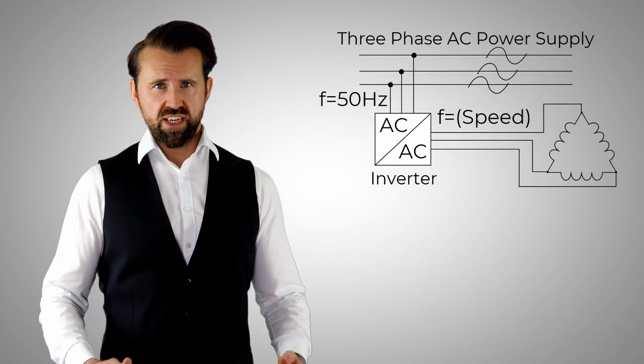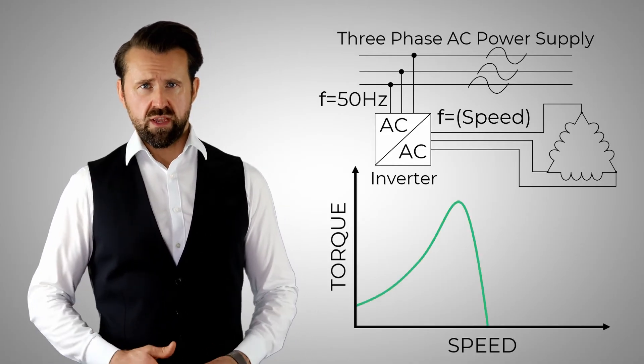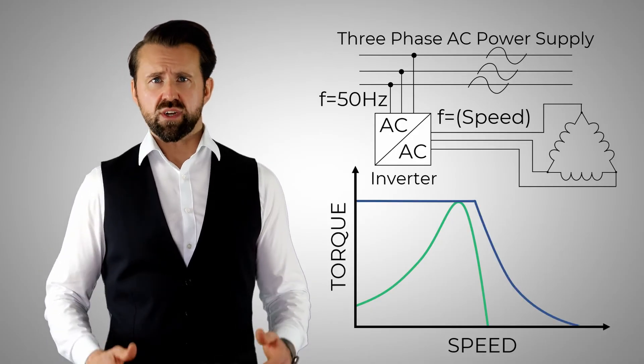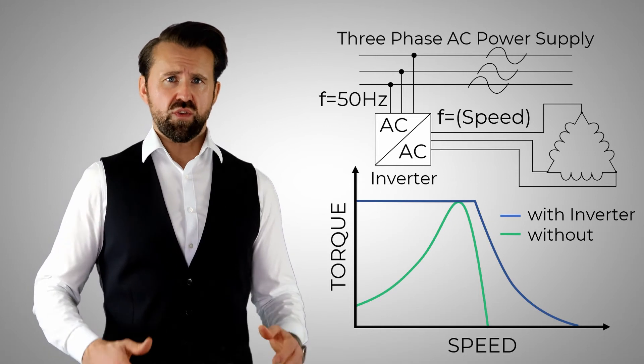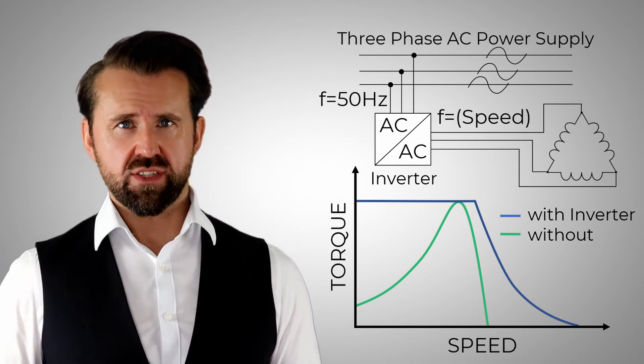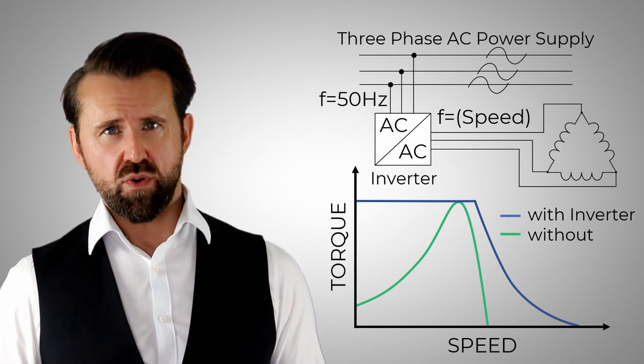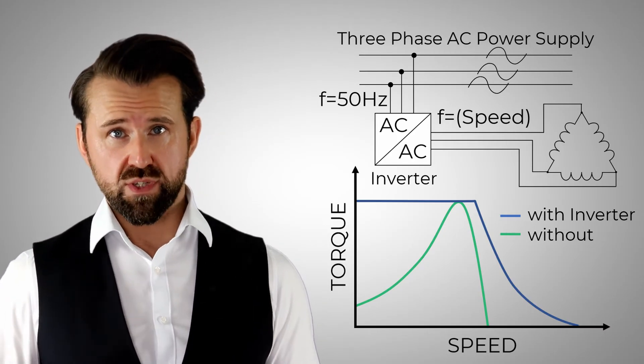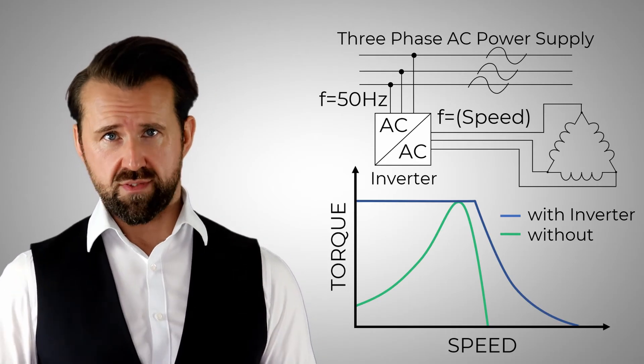The best way to use the full potential of the induction machine is by using an inverter. By using an inverter, the rotational frequency of the stator can be adjusted. This allows a constant torque to be achieved over a long speed range. The inverter takes 50 Hz or 60 Hz from the three-phase network and converts it into an output frequency depending on the motor speed. I have put the link in the description where you can find a direct comparison of all characteristic curves.